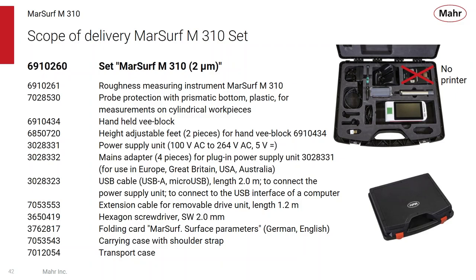The M310 comes in a number of different kits. You can get the kit without the printer, which is what we're showing here. Although the printer is marked off, you get this in a nice case. There's also a transit case that's part of the M310, which you can take out, but you get the roughness instrument, the probe protection, the handheld V-block with adjustments, the power supply, the USB cables, the extension cable for making the drive remote, a folding card of MarSurf surface parameters, the carrying case, and the transport case. This is the version with a 2-micron tip; we also offer this with a 5-micron tip.